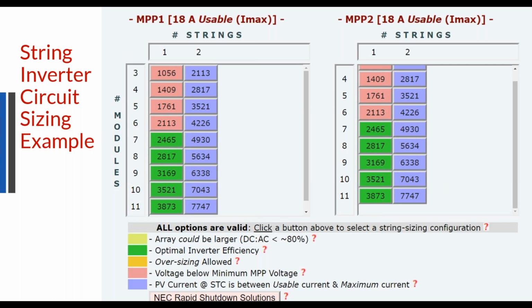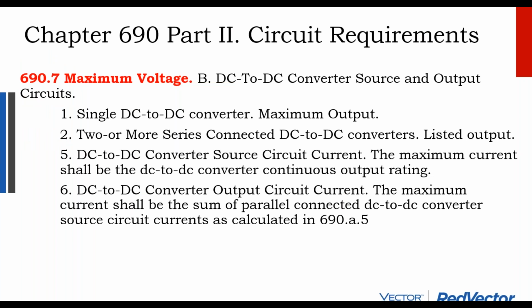And so what that means is if you're in the northern half of the United States where you get into colder weather, you might not be able to have quite as many solar panels on a circuit as you could in the southern half of the United States, because they don't get down into that colder design temperature, so the voltage doesn't rise on the circuits on the roof as readily. So when we get into maximum voltage on a circuit, basically you have to adjust by these temperature correction factors.